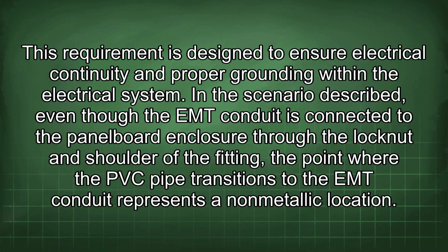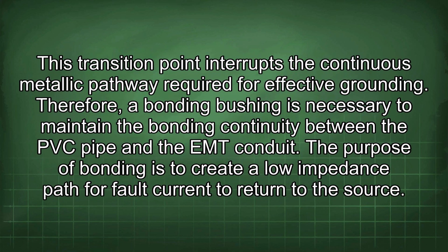In the scenario described, even though the EMT conduit is connected to the panel board enclosure through the lock nut and shoulder of the fitting, the point where the PVC pipe transitions to the EMT conduit represents a non-metallic location. This transition point interrupts the continuous metallic pathway required for effective grounding. Therefore, a bonding bushing is necessary to maintain the bonding continuity between the PVC pipe and the EMT conduit.